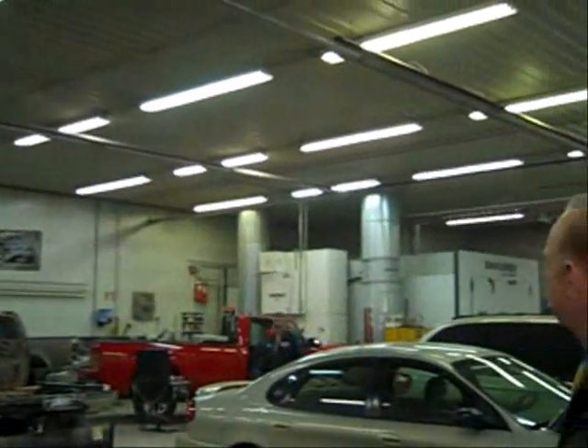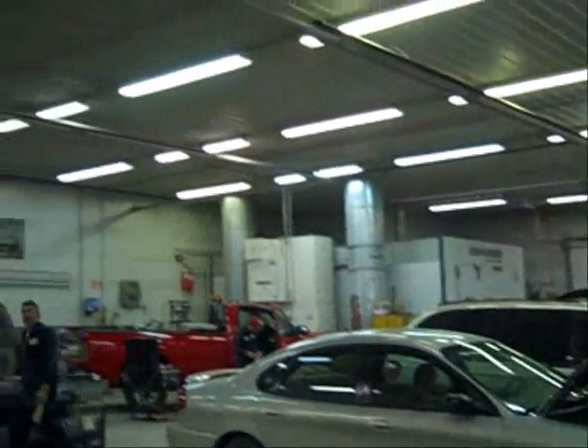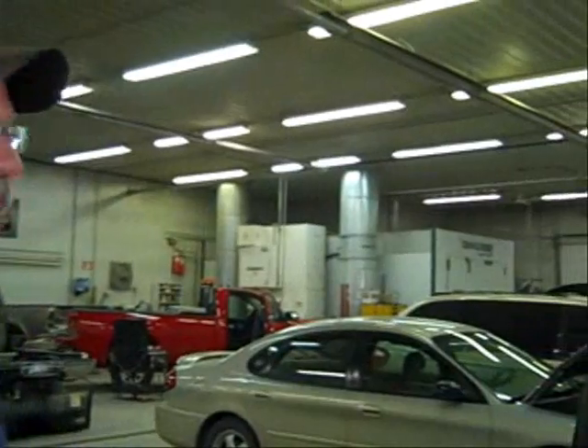We're in the collision shop where we have that system connected, and we just wanted to show the interior with this lighting that's going on. When we were upstairs, we were looking at those inverters, and we were seeing that each one was inputting about 5,000 watts coming back from the solar field. We did the math on it, and it was about 72 amps at 208. This is three-phase power, 208, at 72 amps. So we're pretty much running this whole facility right now off that solar field.